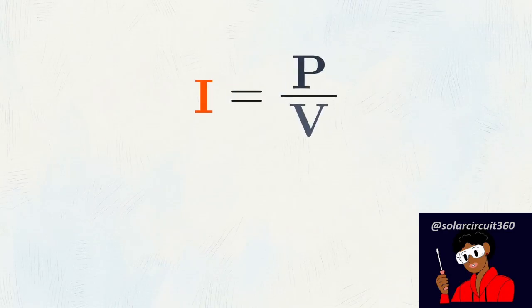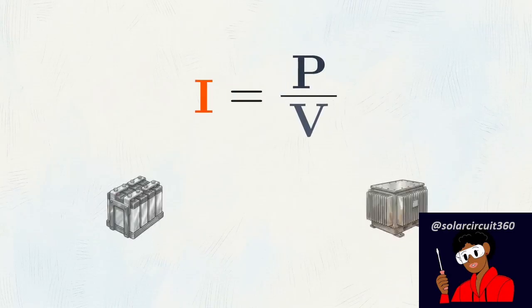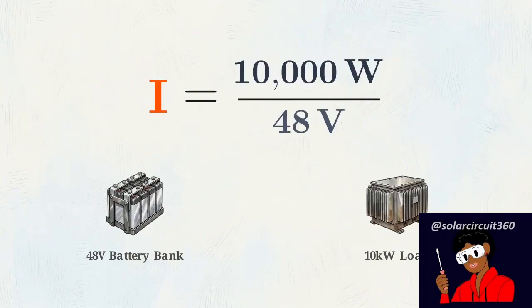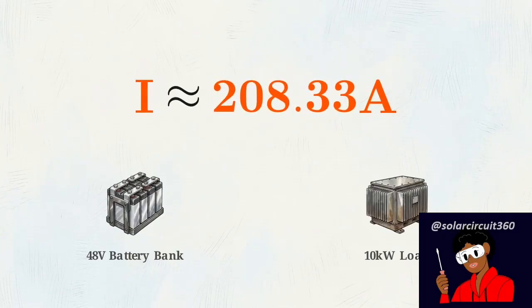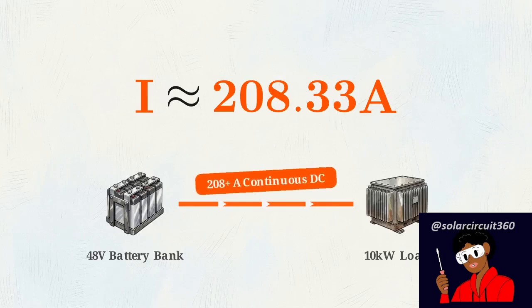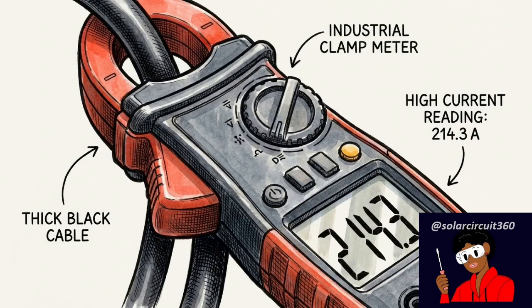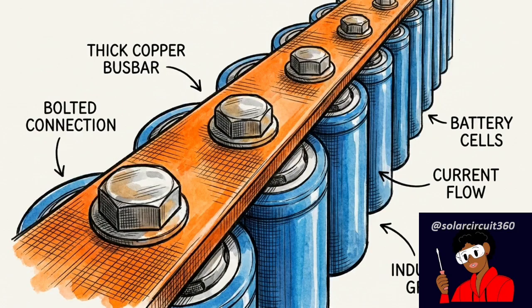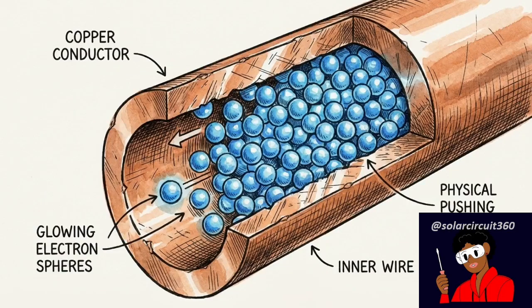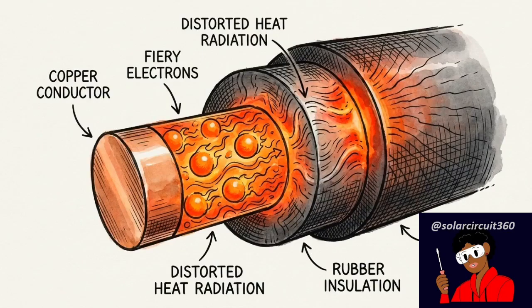Rearranging to isolate current exposes the exact bottleneck of a high-capacity solar setup. Pulling 10,000 watts of power from a 48-volt battery bank resolves to an immense figure, over 208 continuous amps. Pulling over 200 amps of continuous DC current is a punishing, extreme load that tests the physical limits of every component in the chain.